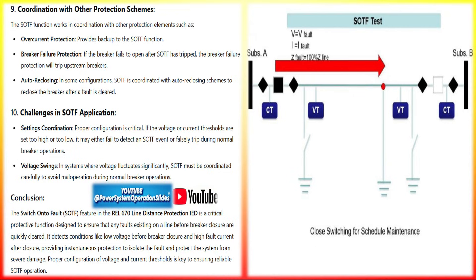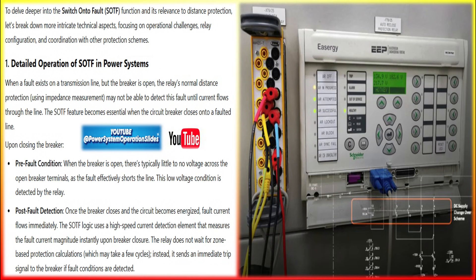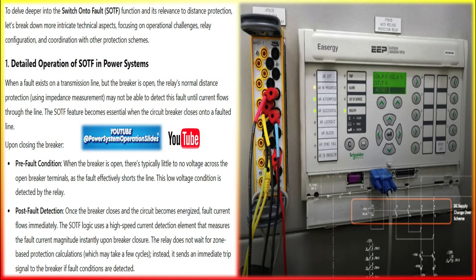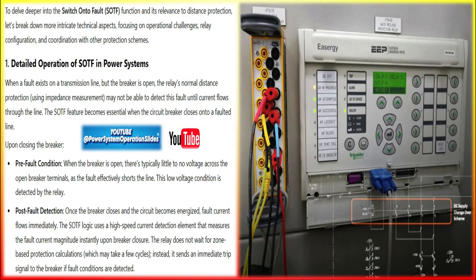In the REL670, the line distance protection IED is designed with advanced features for fault detection, including SOTF. The typical sequence for SOTF operation begins with monitoring the line voltage. The relay continuously monitors the line voltage. Before the breaker is closed, the voltage is near zero if the line is de-energized. If there is a fault, this voltage remains very low.